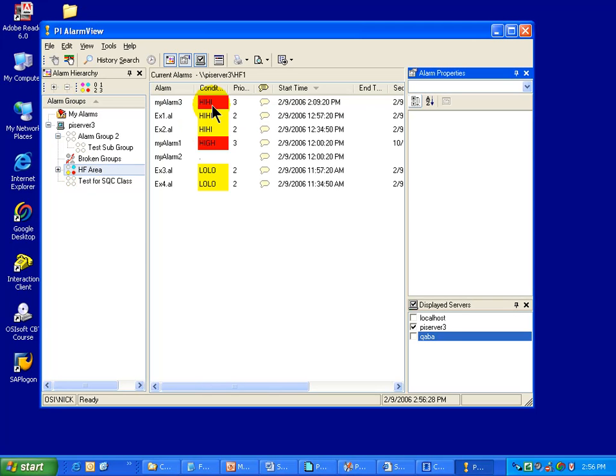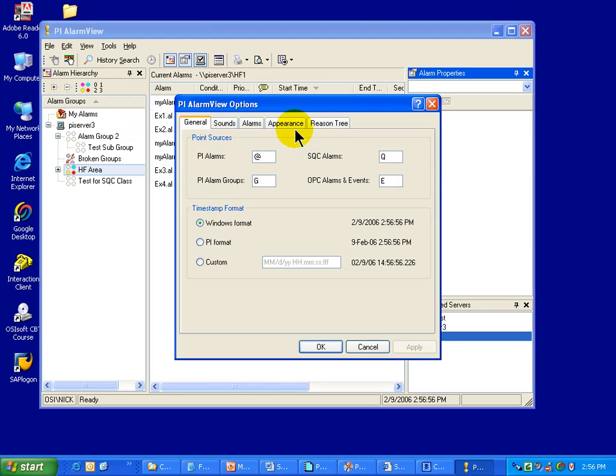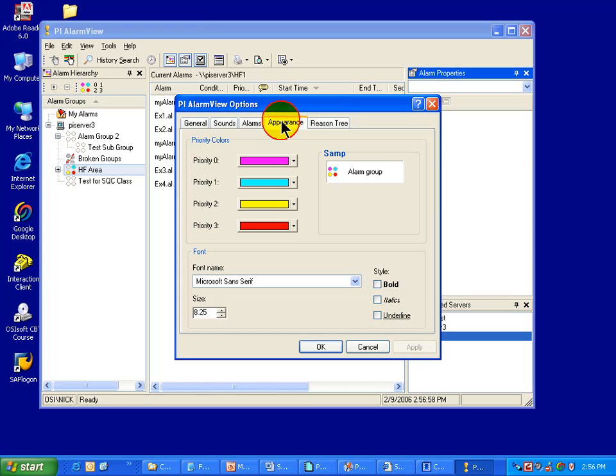The alarms are color coded. You'll notice we've got red and yellow representing Priority 3 and Priority 2. The priorities are not in the order you may think — from our point of view, a priority with a larger number is a higher priority. So the highest priority that Alarm View supports is Priority 3, which is blinking red. You can change the color coding by going into Tools > Options > Appearance.